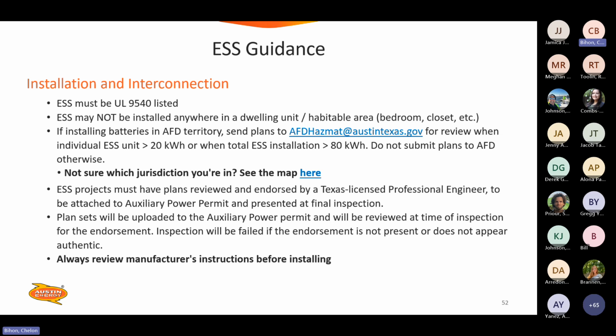ESS guidance, installation and interconnection. ESS must be UL 9540 listed. ESS may not be installed anywhere in a dwelling unit, habitable area, bedroom, closet, etc. If installing batteries in AFD territory, send plans to the given email for a review when individual ESS units are greater than 20 kilowatt hours or when total ESS installation is 80 kilowatt hours or greater. Do not submit plans to AFD otherwise. Not sure which jurisdiction you're in? See the map here.